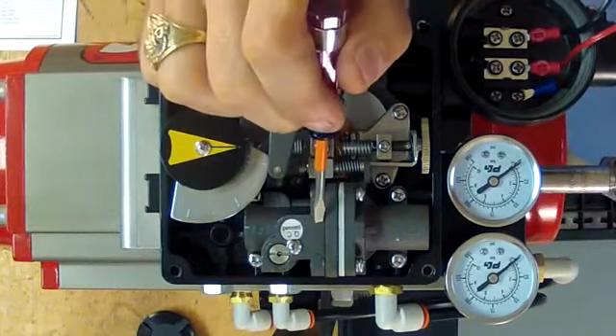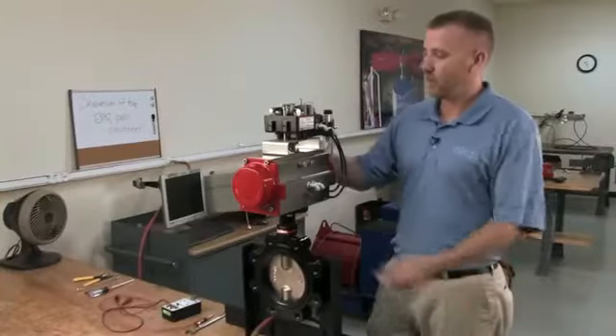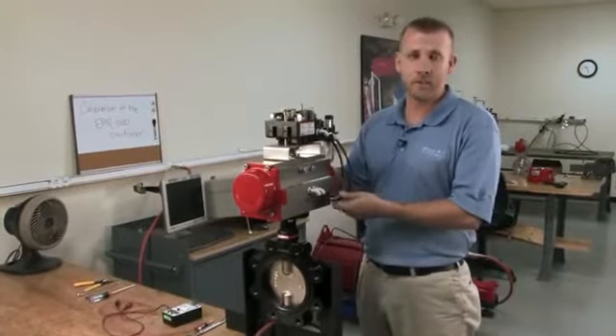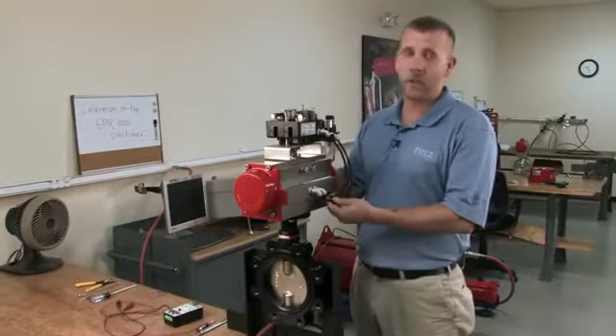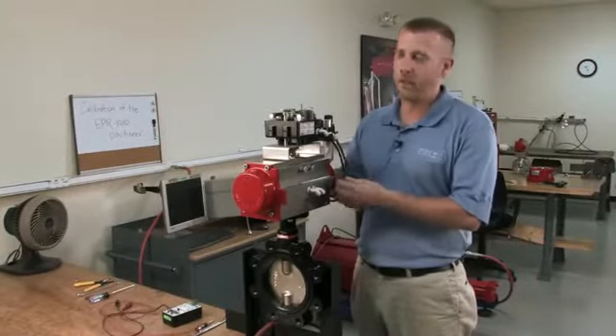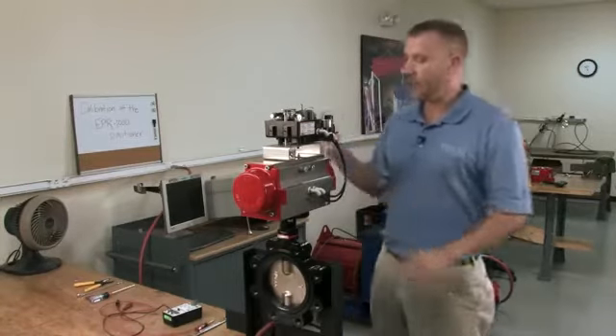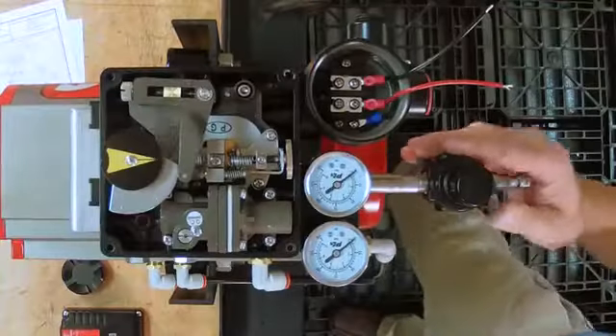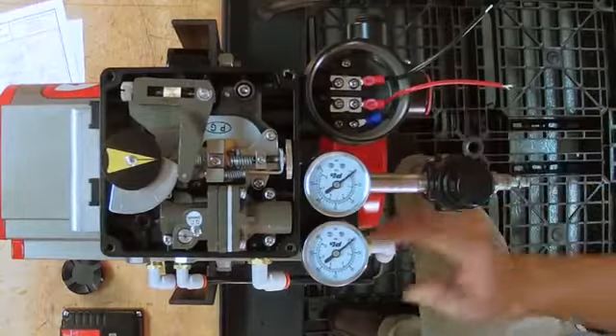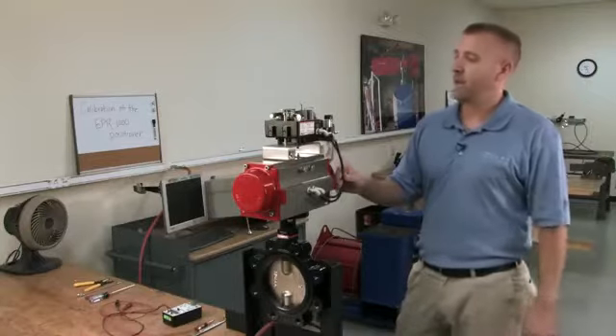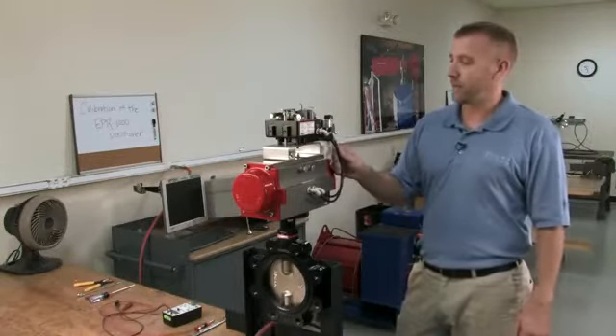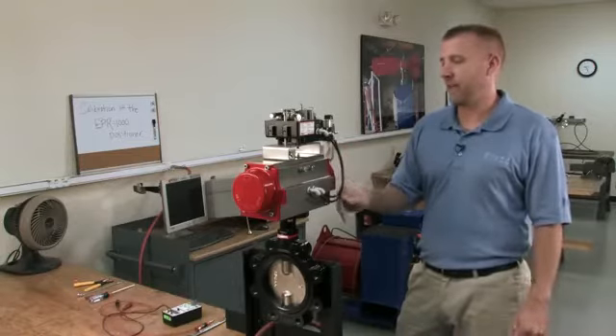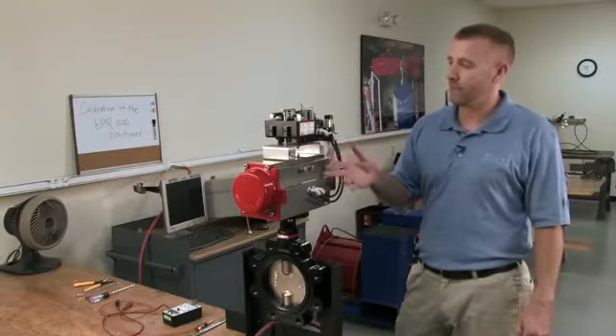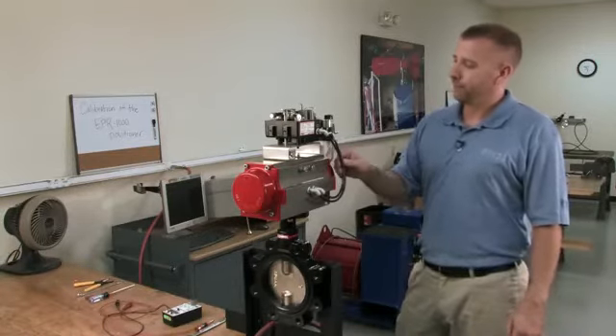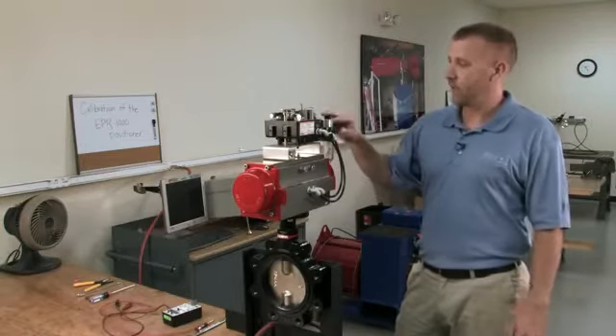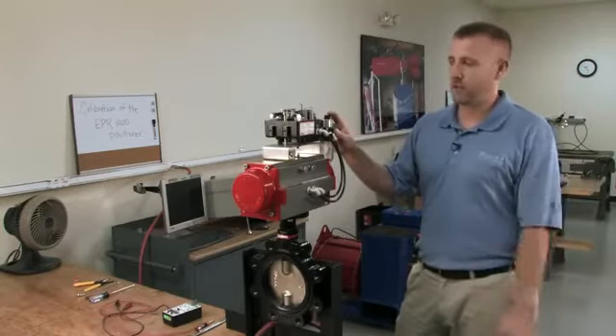and your pilot valve. We offer polyethylene tubing, which is our standard. You can also get stainless steel tubing, copper tubing, and all our positioners, we put a filter regulator on and tube them up double acting. You can tube them up single or double acting. Basically, we do it just to limit the amount of contamination that's introduced into the actuator through the atmosphere. That's why we also put a filter regulator on all positioners that we sell.